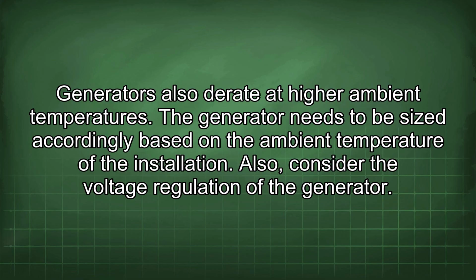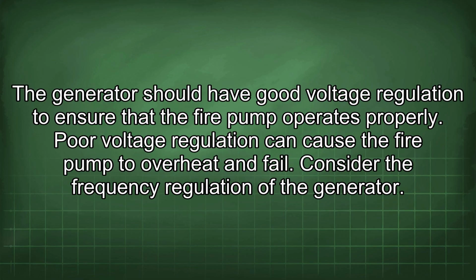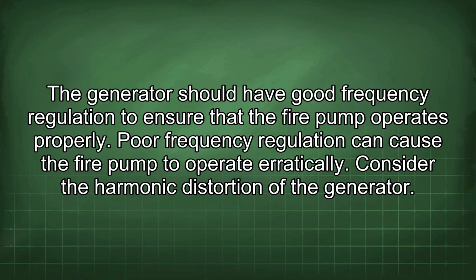Also, consider the voltage regulation of the generator. The generator should have good voltage regulation to ensure that the fire pump operates properly. Poor voltage regulation can cause the fire pump to overheat and fail. Consider the frequency regulation of the generator. The generator should have good frequency regulation to ensure that the fire pump operates properly. Poor frequency regulation can cause the fire pump to operate erratically.